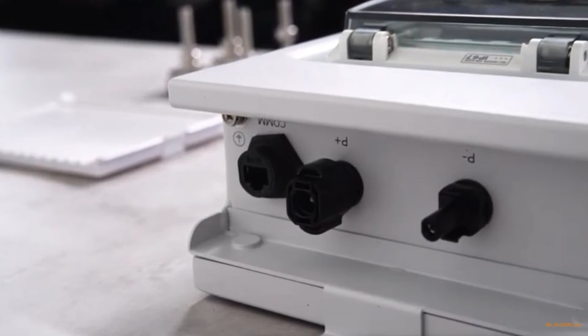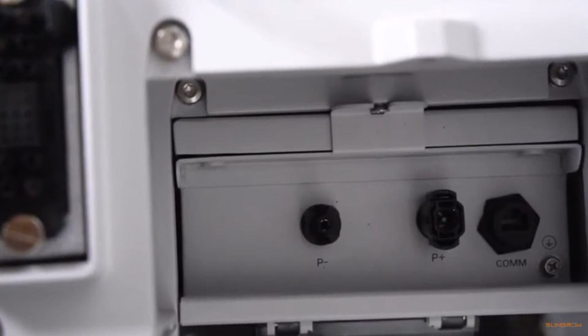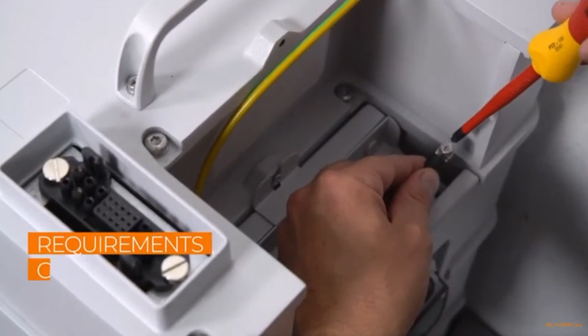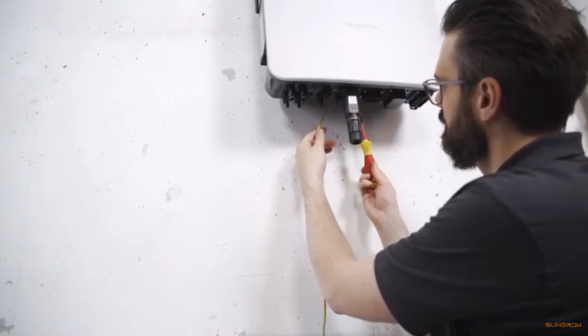You'll need the included M4 screws for the wall and M5 screws for the module. Now let's come to cabling. The battery has 4 connectors: grounding, P+, P-, and one terminal for communication with the hybrid inverter. Let's start with the grounding. Fix it on the battery side and connect it to the ground at the bottom of the inverter.